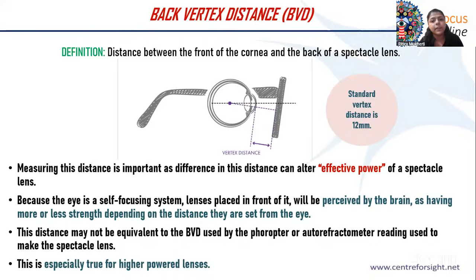Now, how can this be measured? Historically, the instrument used to measure the vertex distance was called the distometer. In this, we basically ask the patient to close their eyes. The device, as you can see, is placed between the lid and the spectacle lens. The plunger is slowly pressed so that the two ball ends separate. When they touch the lid as well as the back surface of the lens, we read the marking on the scale.